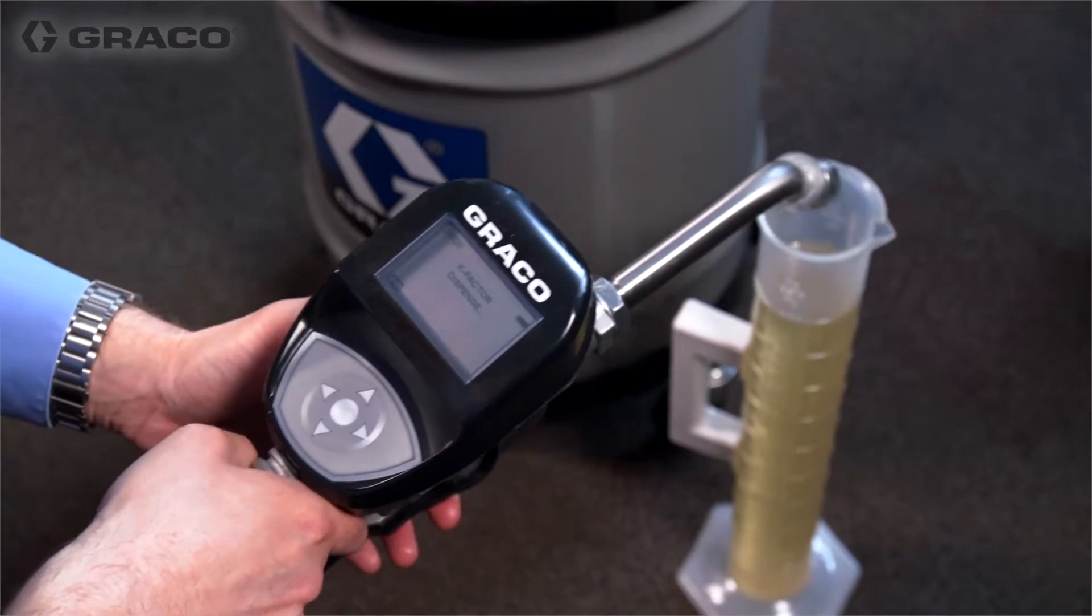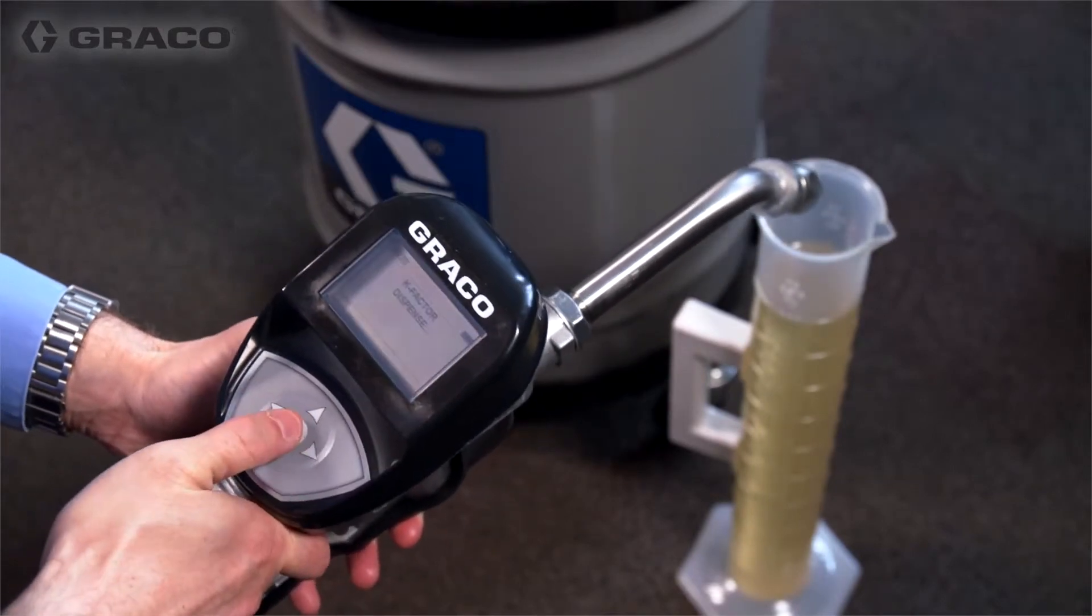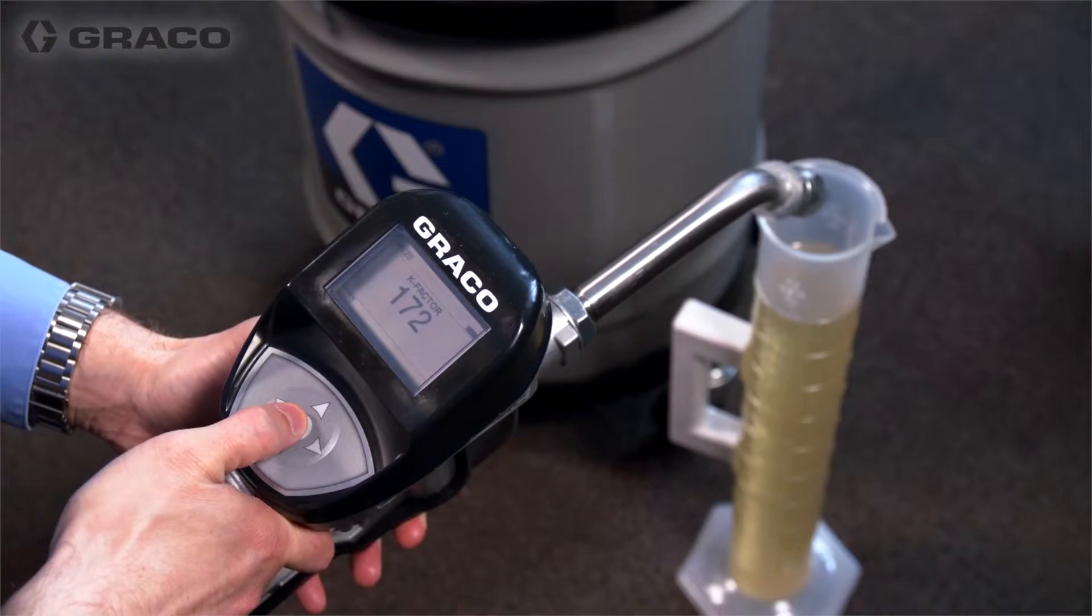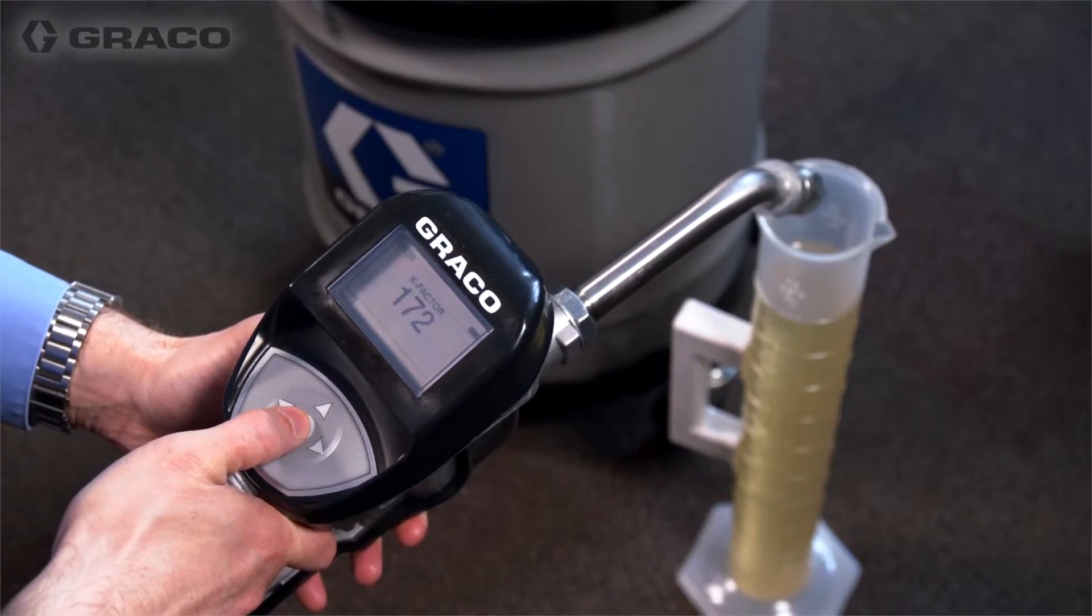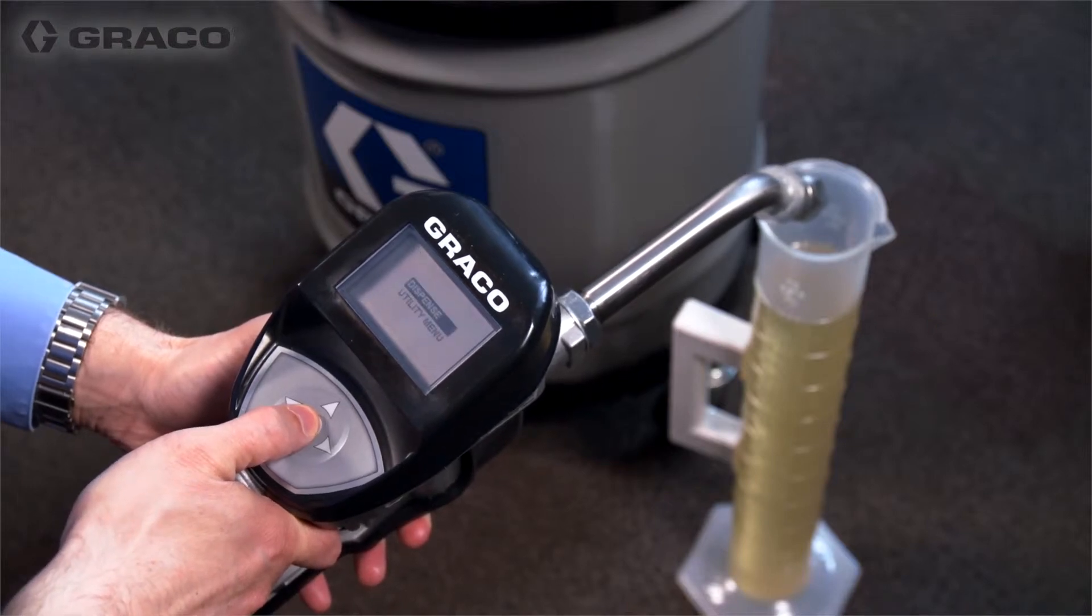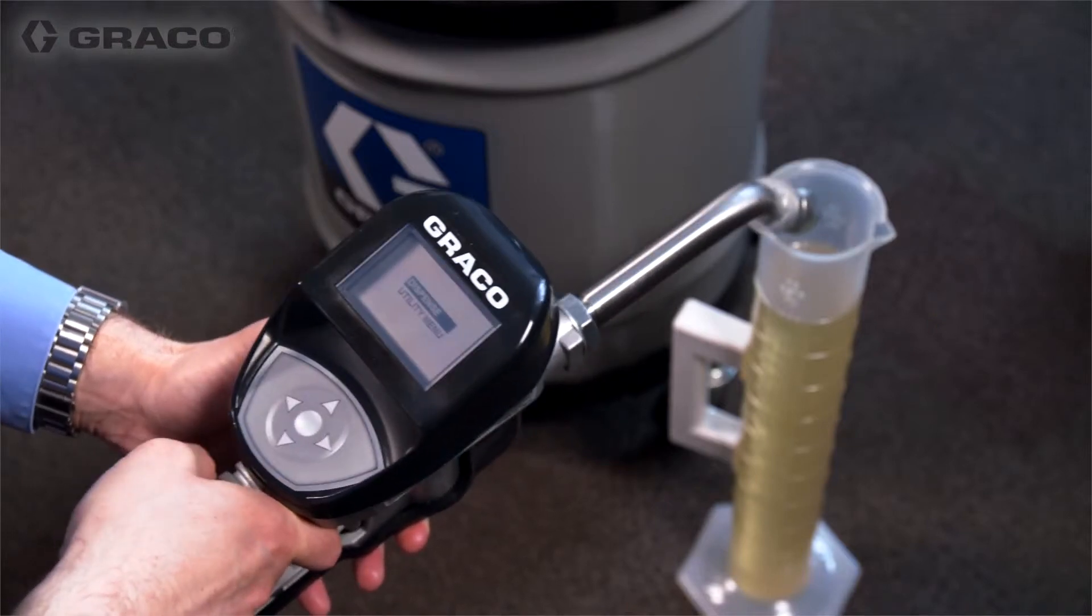When exactly one quart or one liter of fluid is dispensed into the container, press the Enter button on the keypad to select End. A screen displaying the quantity of fluid dispensed displays. Press the Enter button on the keypad again to select End and save the new calibration factor.